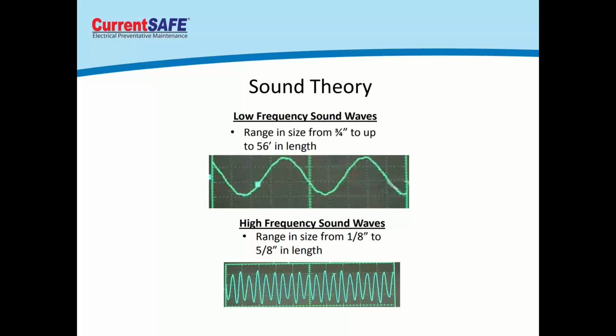Low frequency sounds are easy for us to hear, but if we're hearing them in that under 16 kilohertz range of audible hearing, that means the severity of an anomaly has already reached a point where replacement is probably necessary, and we can't do anything in the predictive realm of electrical maintenance. So we want to use this high frequency sound wave in the 20 to 100 kilohertz range to detect electrical anomalies as early as possible. I'll cover a predictive maintenance chart in just a little bit to show everybody why that early detection is so important.